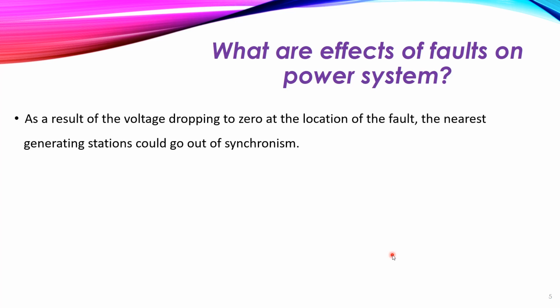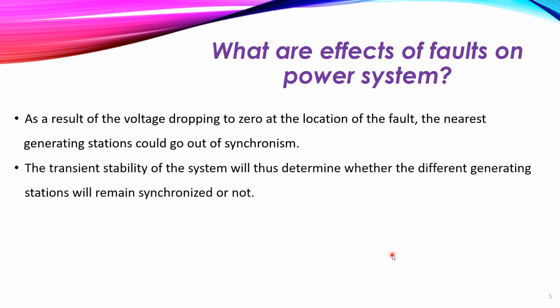zero at the location of the fault, this will cause the nearest generation station to go out of synchronism with the power system itself. Also, the transient stability of the system will determine whether the different generating stations will remain synchronized with the power system or not. This depends on the analysis of the transient stability of the system. So, by analyzing the delta angle for the generator, we can determine the time at which our generators will stand and remain in synchronism.